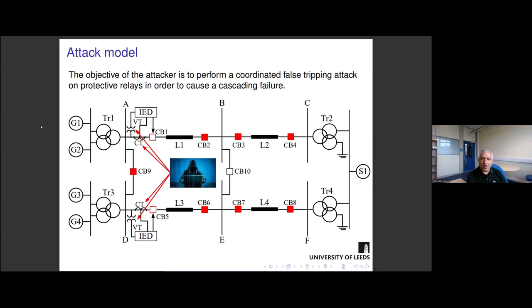The attackers can also attack the commands that come directly from IEDs, but we didn't consider that because the commands from IEDs can be authenticated, basically. But for the measurements, because we have a high number of measurements, for example, 4,800 SV packets, it would be very difficult to use authentication and encryption for those types of data because it will cause delays beyond the acceptable levels that we have.